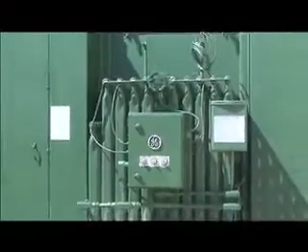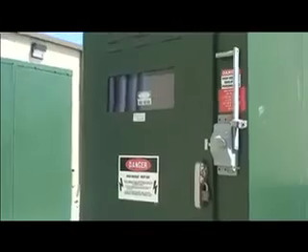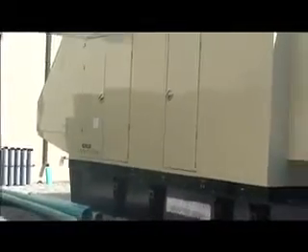Liberty Center One is connected to Detroit Edison through our private 2.5 MW primary transformer. In the event of a loss of primary power from Detroit Edison, the dual UPS system will carry all customer and critical system load until the dual backup generators come online. We have 20 to 30 minutes of battery time at full data center capacity.